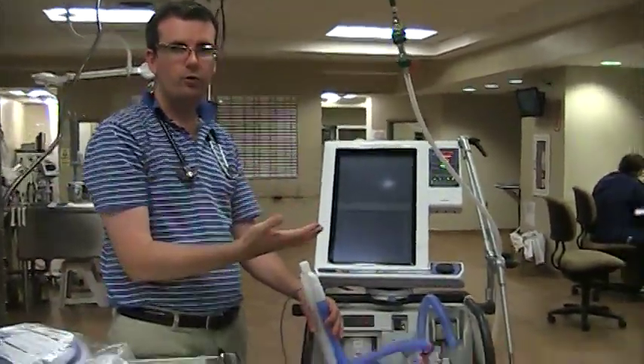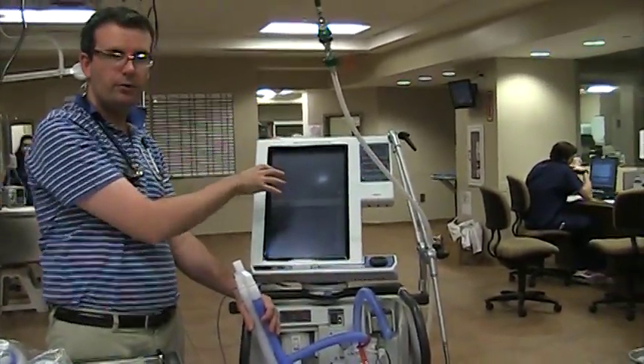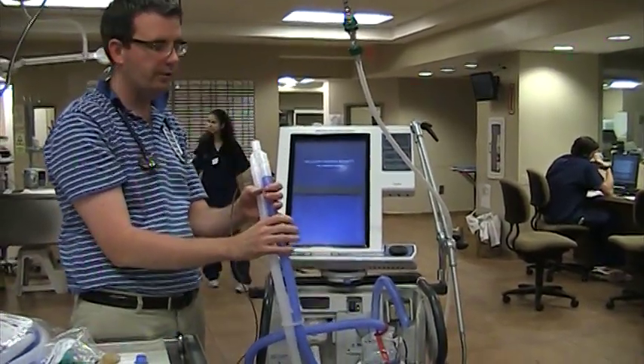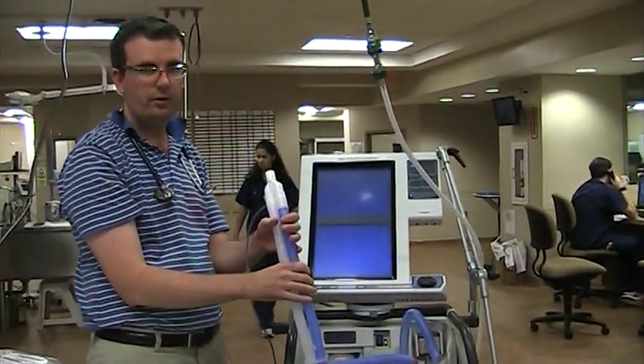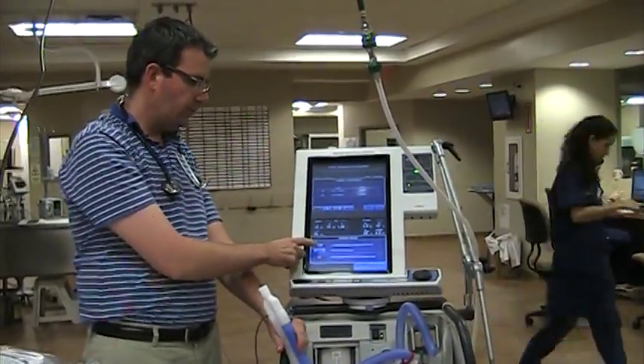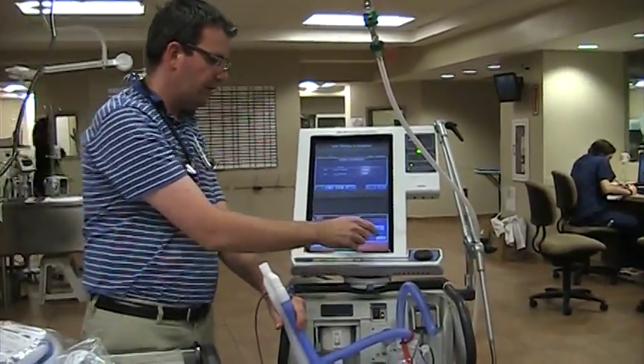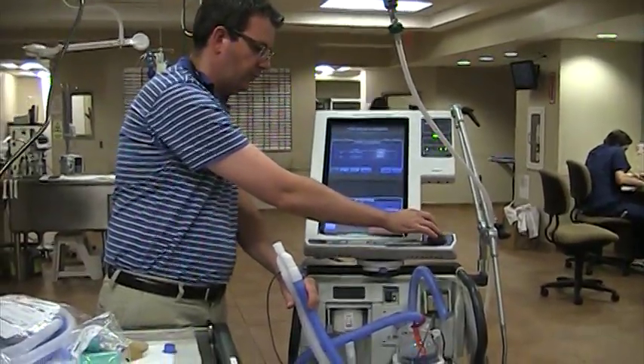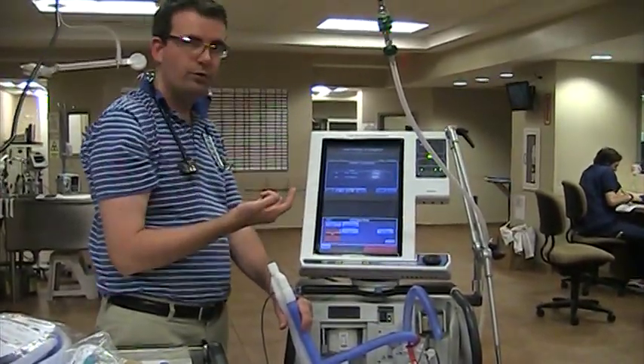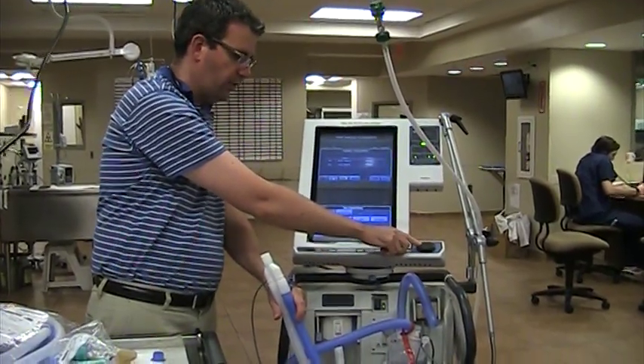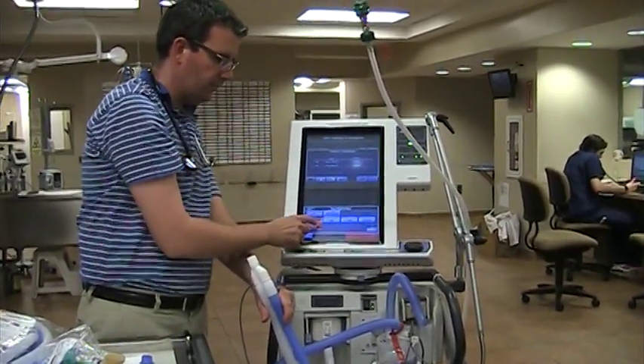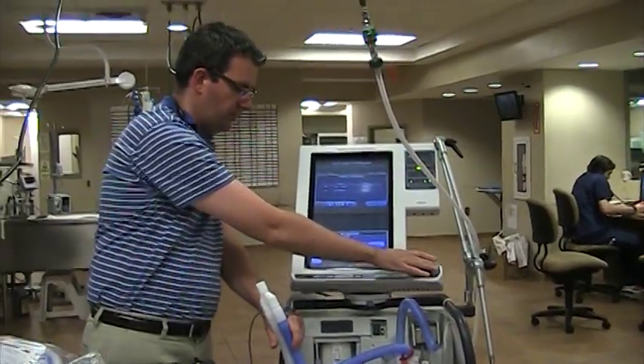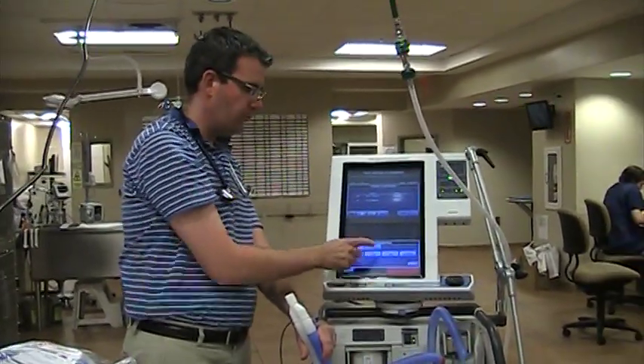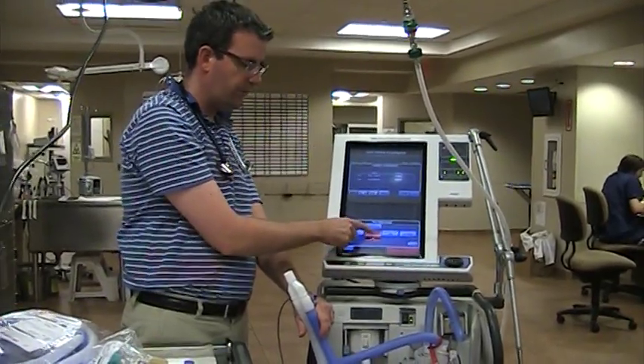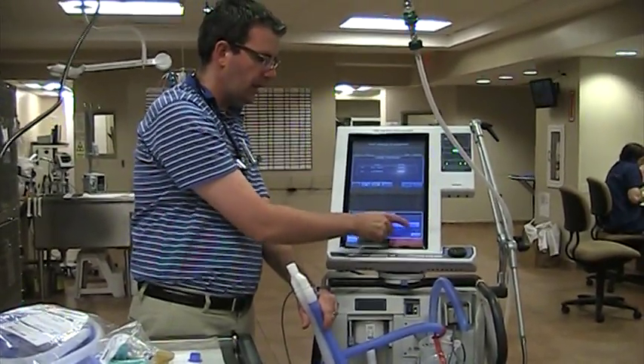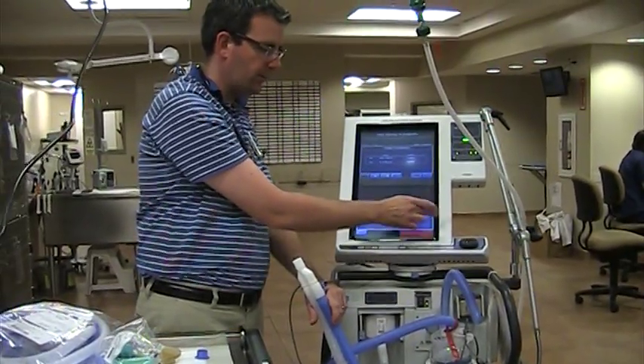And the machine is going to shut itself down. It's going to save those settings so that it knows what the compliance is and what the resistance is in the tubing. Now we just choose new patient. We dial in the weight right here, so we can change the weight to whatever it is in kilograms. We can choose the mode, whether it's assist control, SIMV, or spontaneous. So we'll choose SIMV for now. We can use volume control versus pressure control, so PC versus VC. And usually we don't have to worry about this part here, and then we press continue.